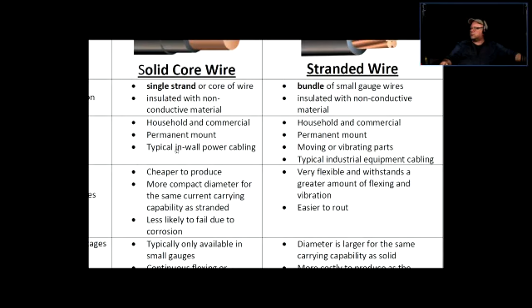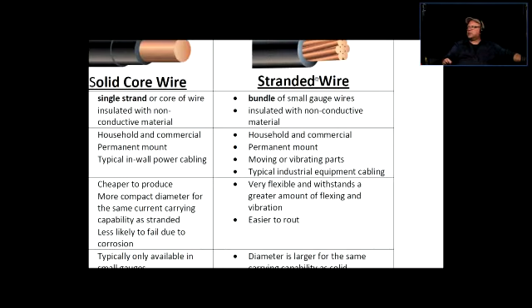Why do we use stranded wires in industrial equipment or moving and vibrating parts? If the cable is stranded, it does not transfer the vibrations along its length, and it stays more put in screw terminals or other connections. It's more flexible. Whereas the solid cable would transfer the vibrations along its length, which could cause loose connections or even wire breakage. If you look under the hood of your car, you'll find stranded wires, because the engine sends a whole bunch of vibrations, and stranded cable is the choice of wiring there.